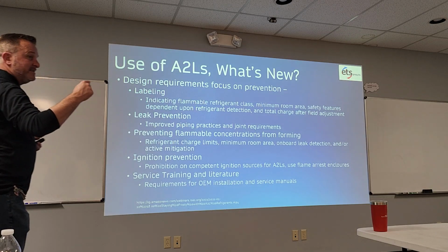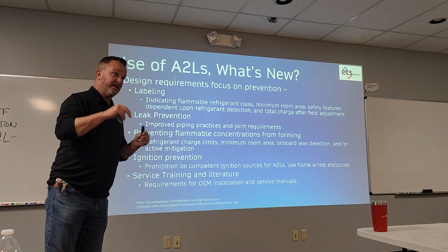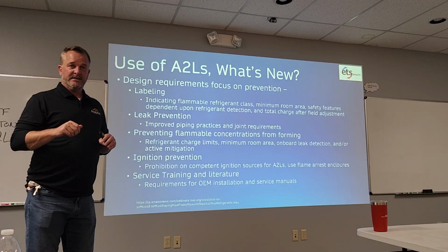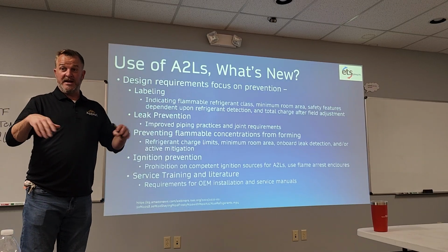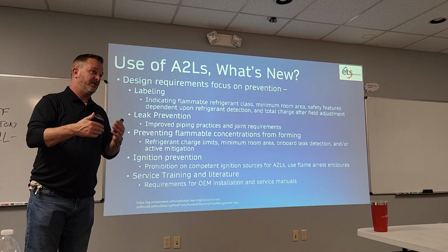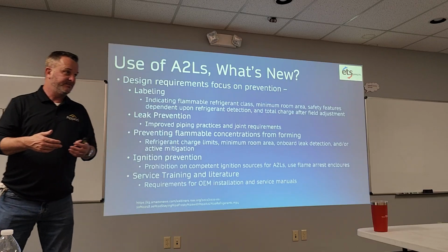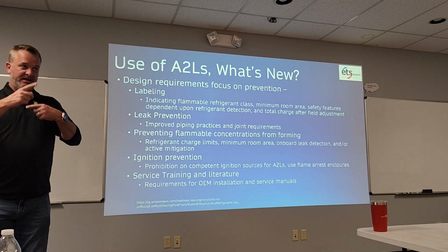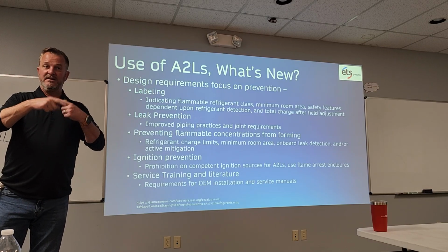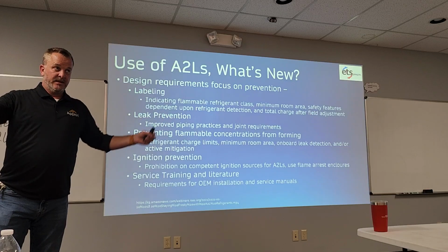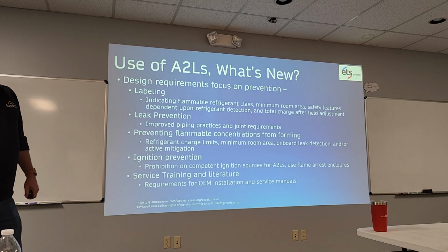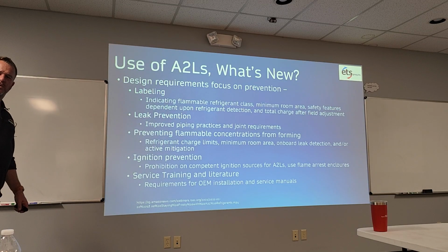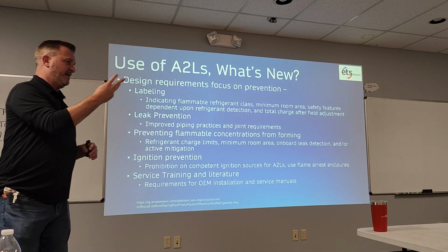So once that leak detection system detects a leak, and again, this is where it differs a little bit, some systems might just shut down depending on the manufacturer. This is where you have to read the manufacturer's information. But what'll happen is the blower motor kicks on, right? And it's going to dissipate the refrigerant throughout. Now, I know Carrier, I believe, I was watching their videos, and I can send this over to you if you want too. He actually does a really nice little demonstration of this. I believe Carrier does it 3 times.